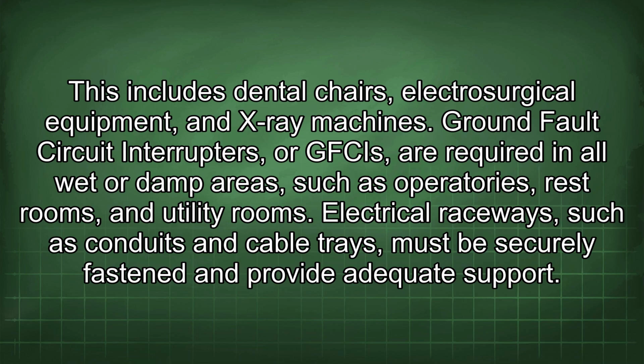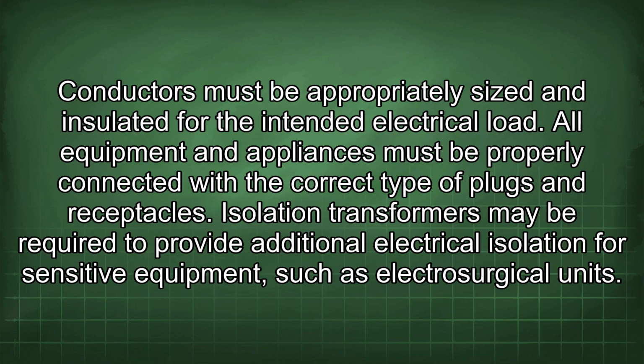Ground fault circuit interrupters, or GFCIs, are required in all wet or damp areas, such as operatories, restrooms, and utility rooms. Electrical raceways, such as conduits and cable trays, must be securely fastened and provide adequate support. Conductors must be appropriately sized and insulated for the intended electrical load. All equipment and appliances must be properly connected with the correct type of plugs and receptacles. Isolation transformers may be required to provide additional electrical isolation for sensitive equipment, such as electrosurgical units.